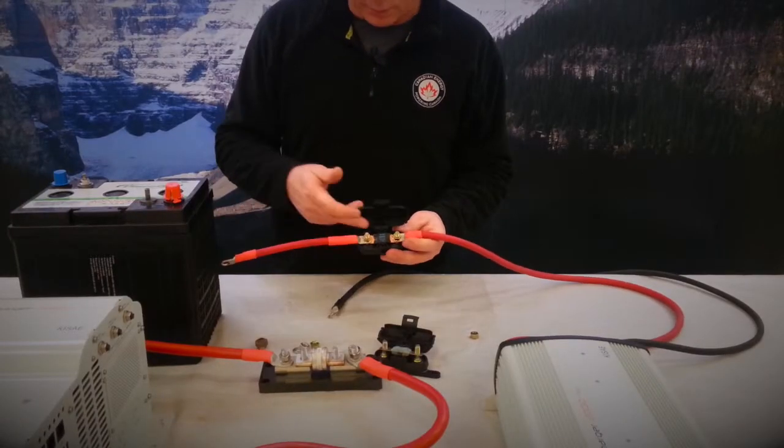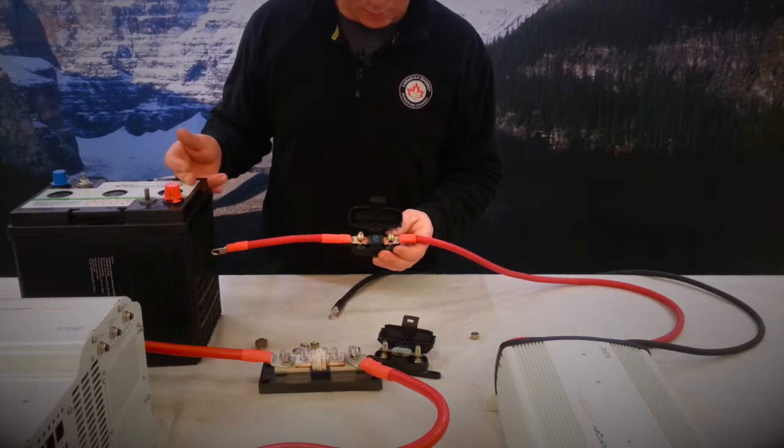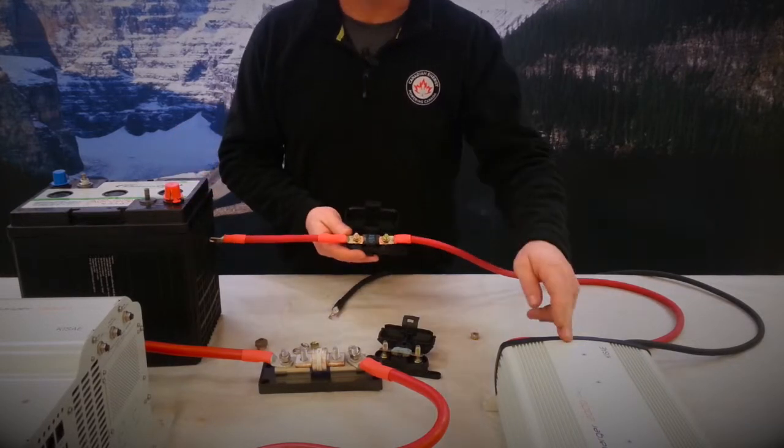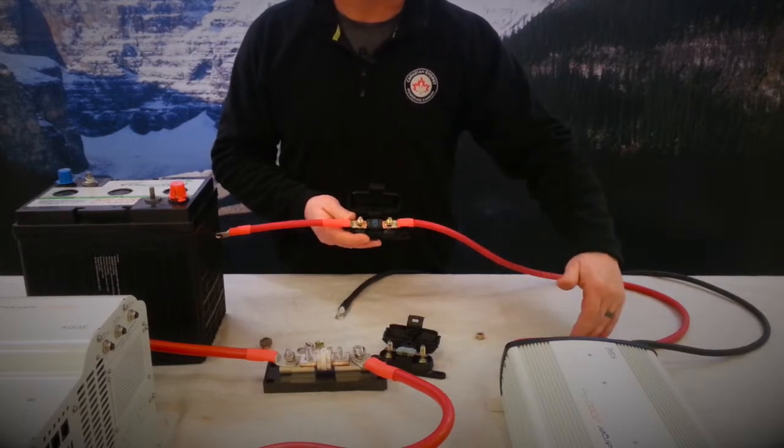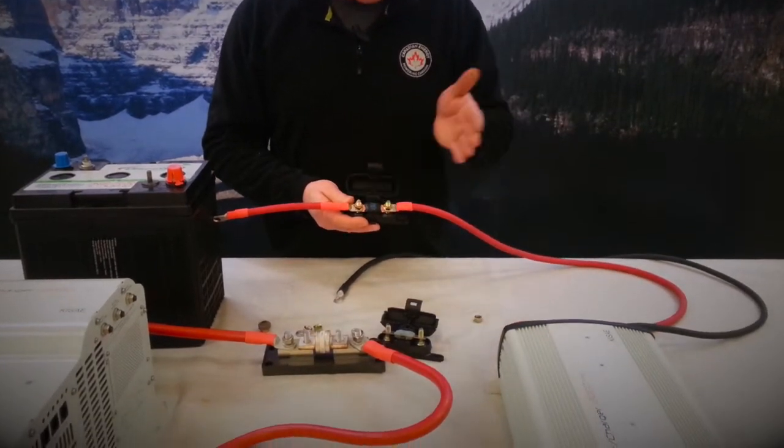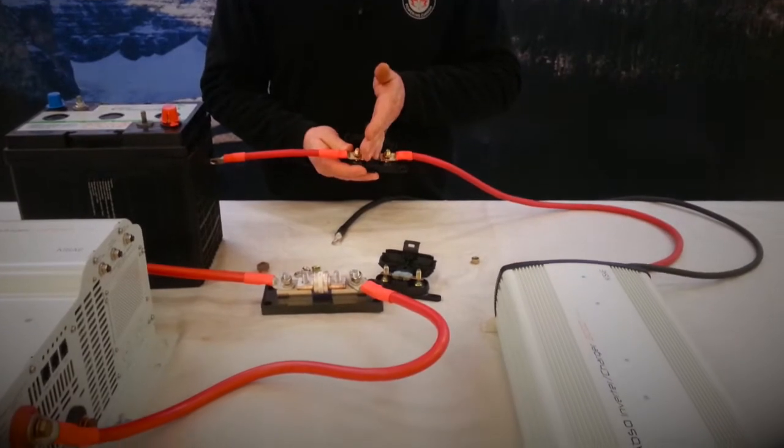So the reason we keep the fuse as close to the battery as possible is we're not trying to protect the inverter, but we're trying to protect the cable that runs to the inverter. If by chance this cable gets shorted, we're close to the battery, we're actually going to trip the fuse very quickly.